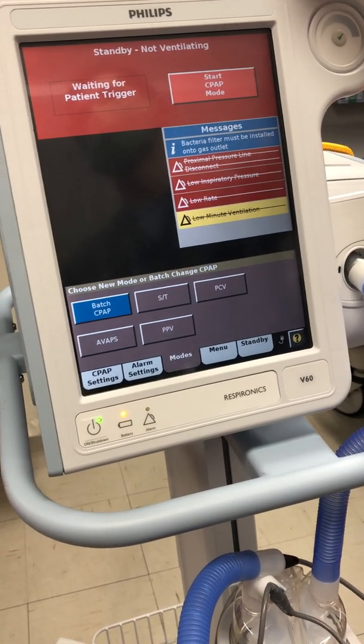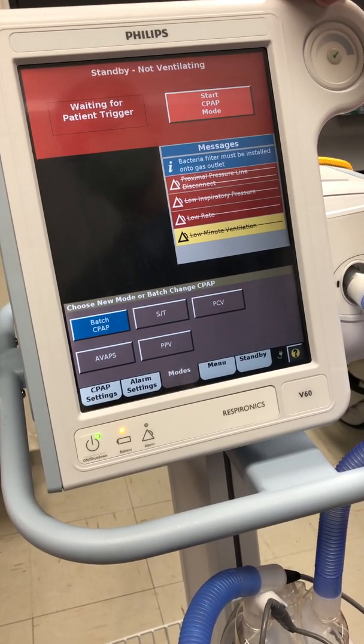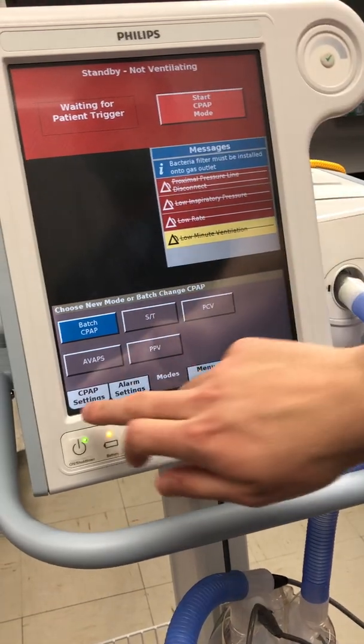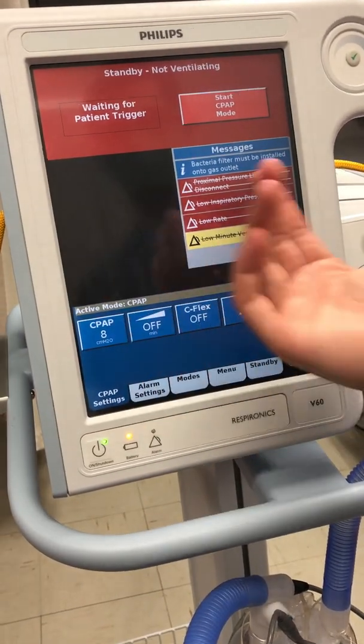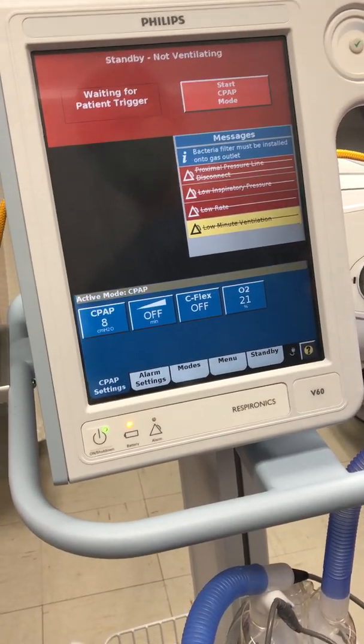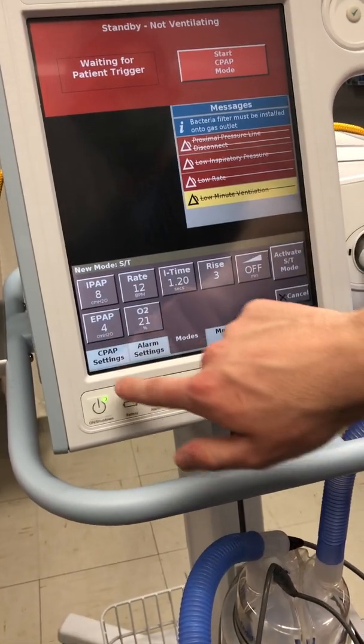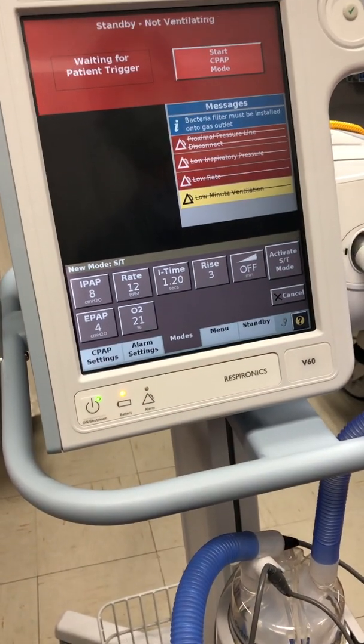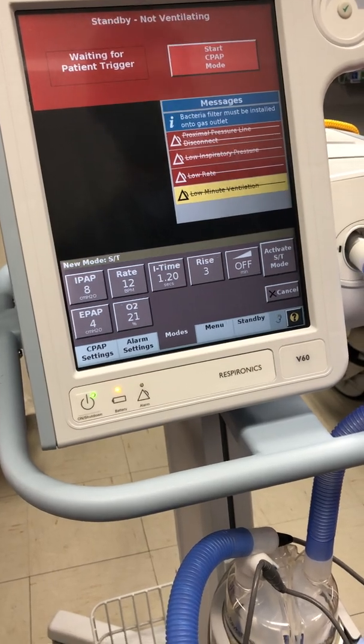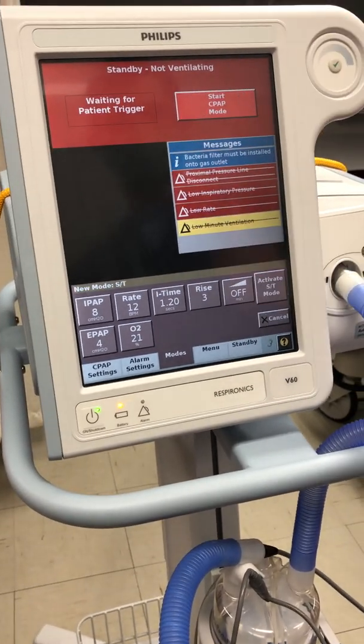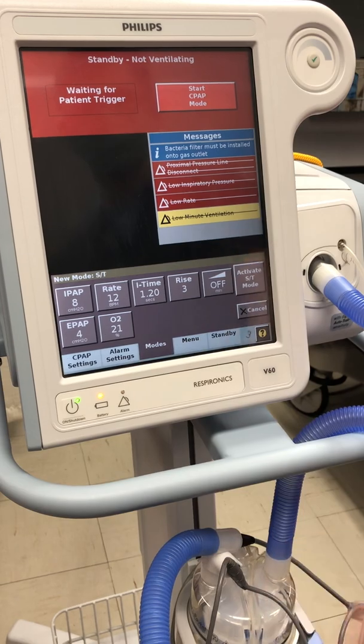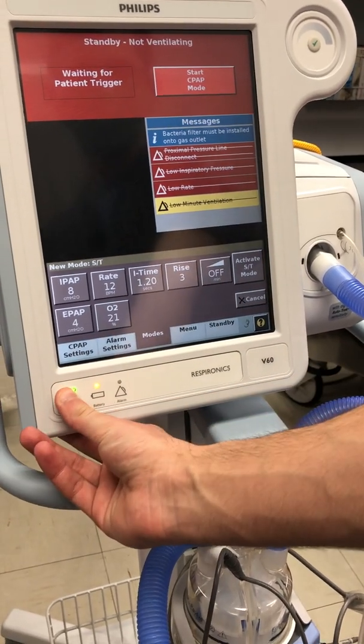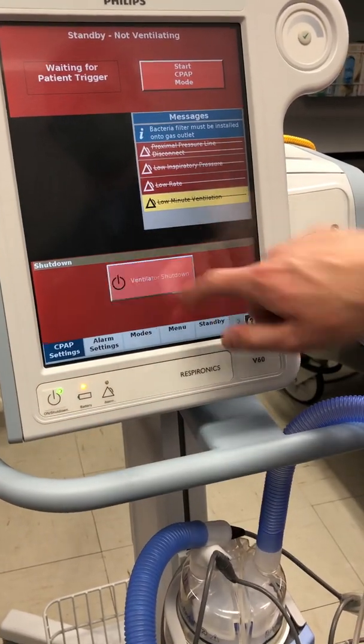Oh, what am I saying? The alarm settings are going to be the exact same as the ventilator settings. The actual settings for the CPAP will be 8 or whatever you need to be. For the modes, whatever you need your settings to be here. To turn it off, make sure it's in standby. And I think you press and hold that button, and then you gotta press this. Self-explanatory.